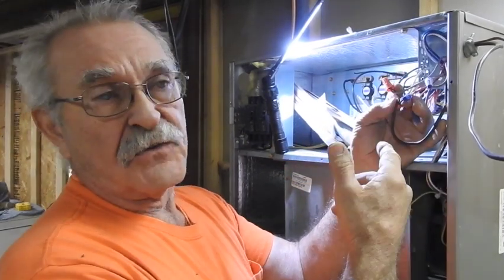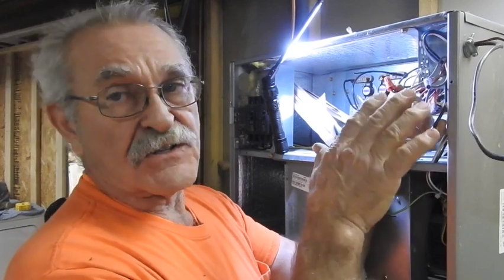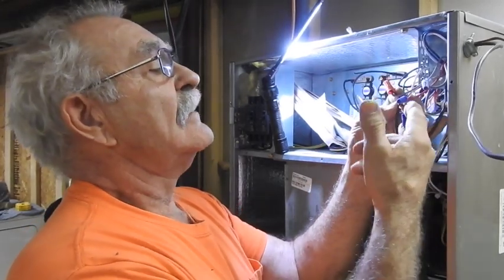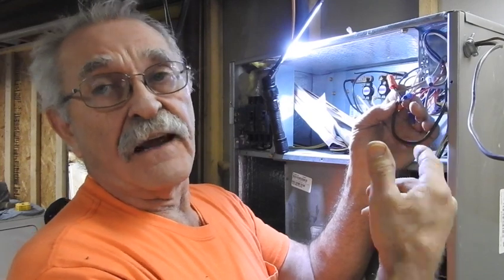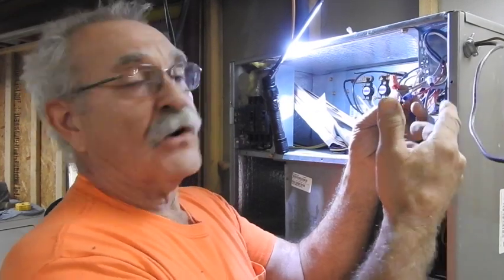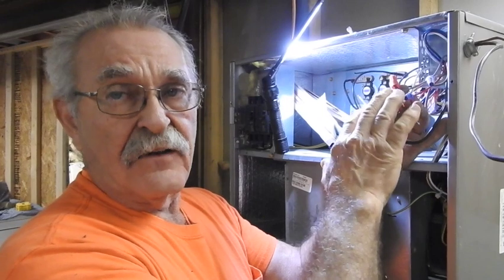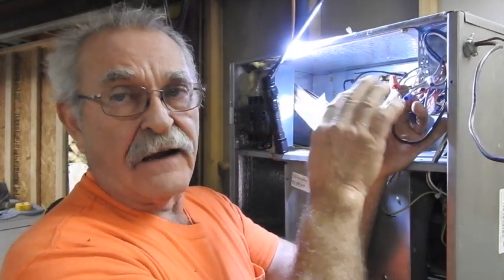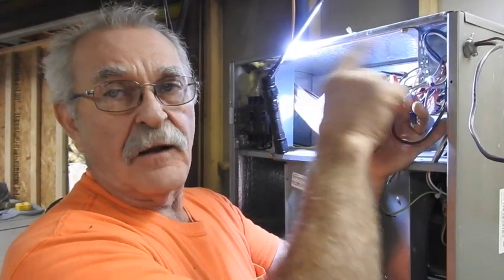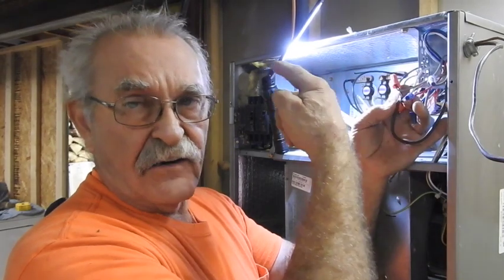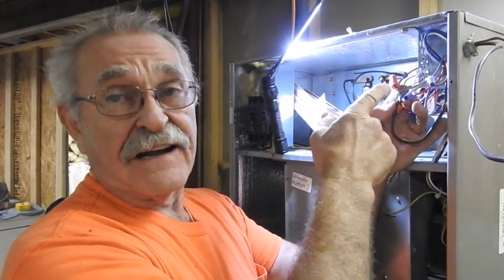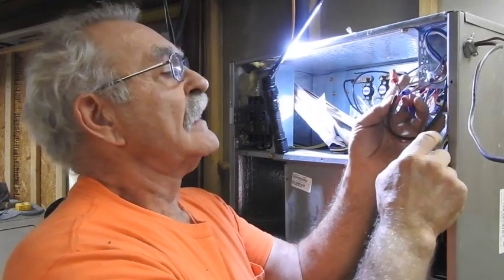Green is the generally accepted term across the industry to energize your fan, and yellow energizes the air conditioner. The yellow comes back and can either go to a terminal board then outside, or it can go outside first, then come back in and tie the other side of what goes outside to the other side of the transformer to complete the circuit.